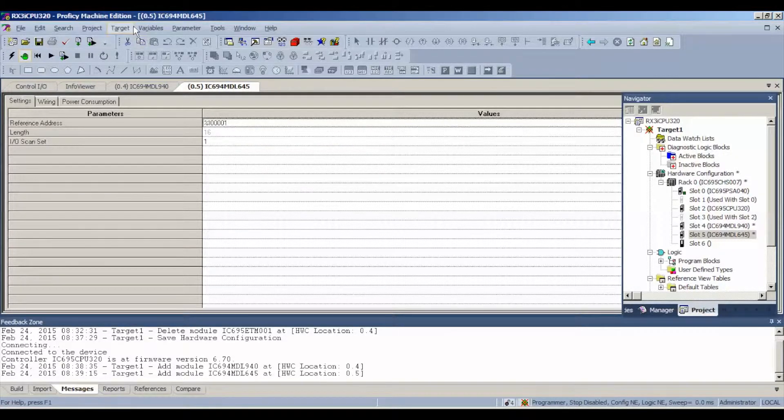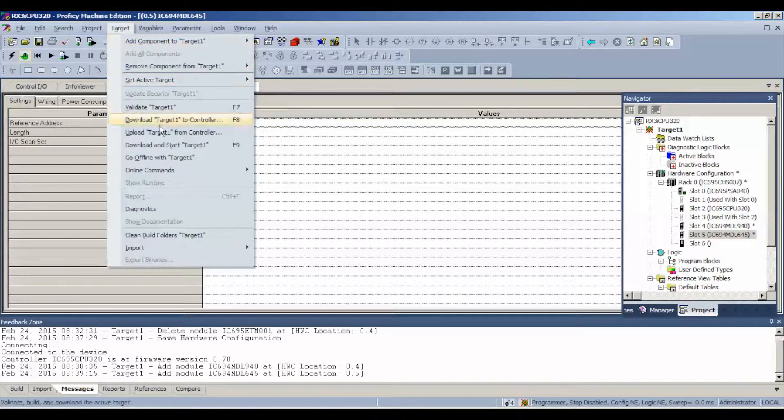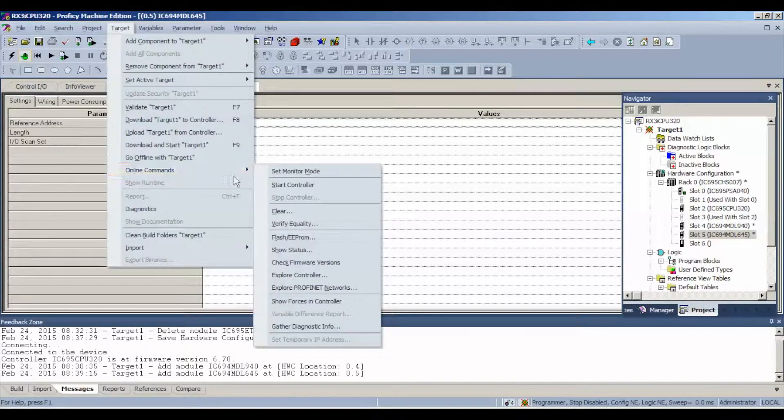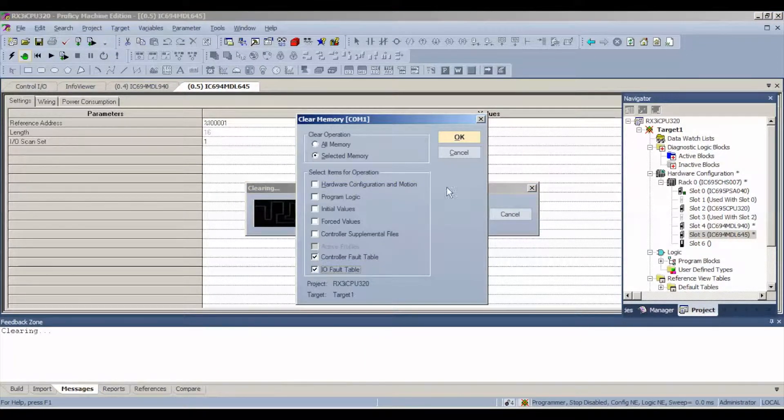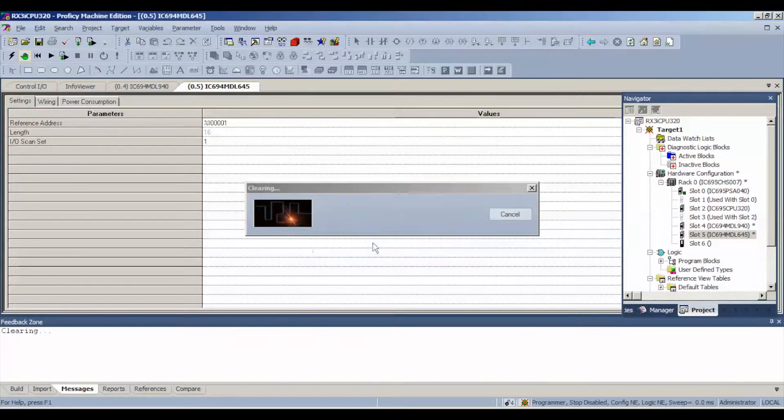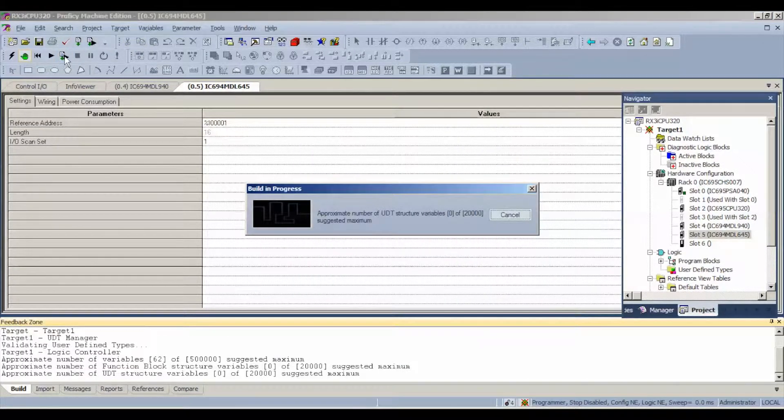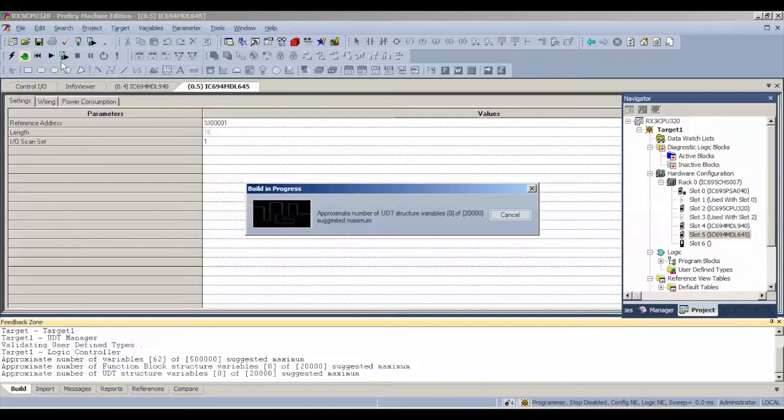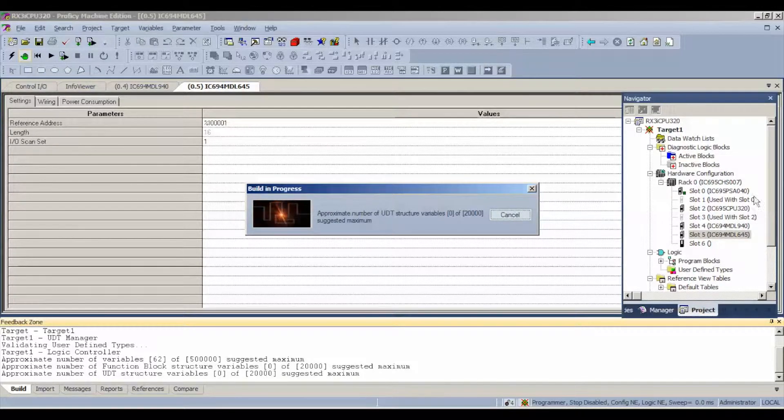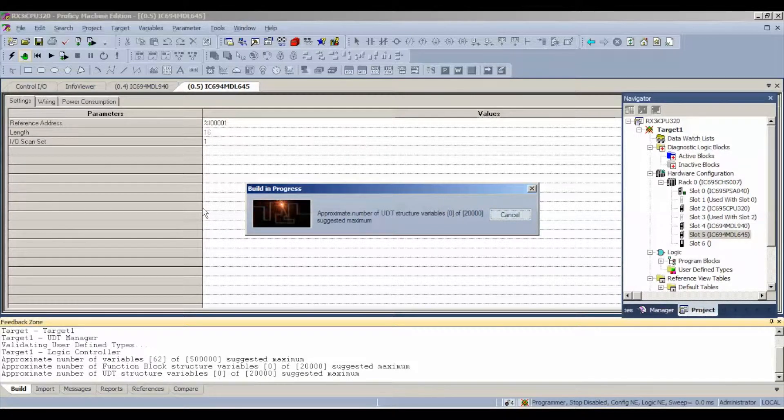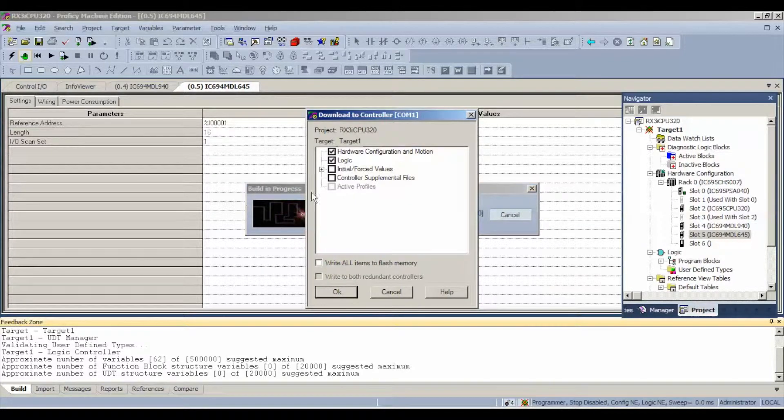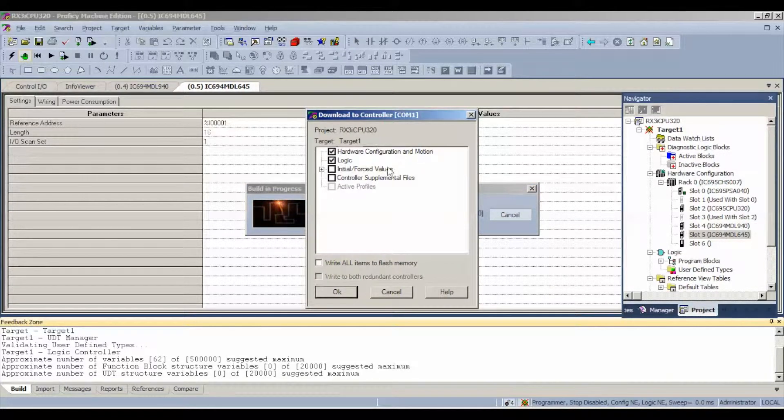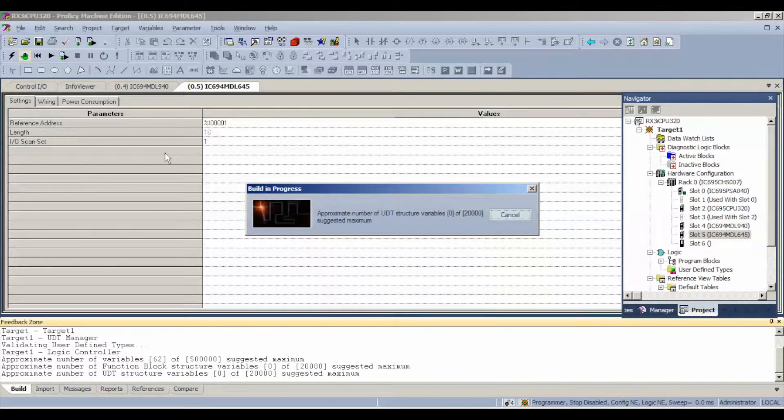The next thing I want to do is go to target. As I said before, logic and configuration are not equal. What we'll need to do is go to clear. We're going to clear controller fault and I/O fault tables. That's because the processor was doing something different before. Then we're going to click download and run. We're going to download this configuration which is just a hardware configuration. When the software asks us exactly what do we want to download to the processor, it's just hardware configuration, motion, and logic. We don't want to write anything to permanent flash memory or anything like that.